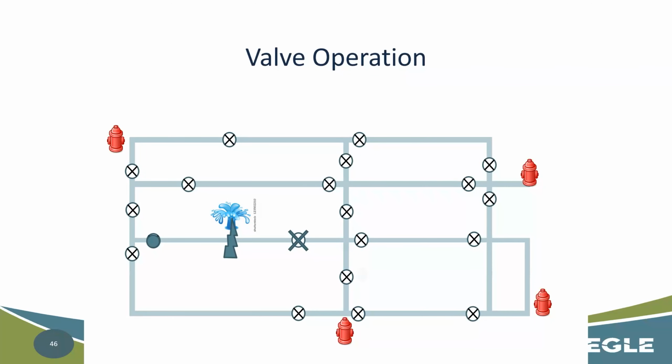So then we move to other valves. We're able to get success out of these two valves. That's excellent. They closed up nicely for us. We tried this third valve, not so good. Didn't get closure, had an issue. Move out to the next two valves. Finally, we were able to get isolation.